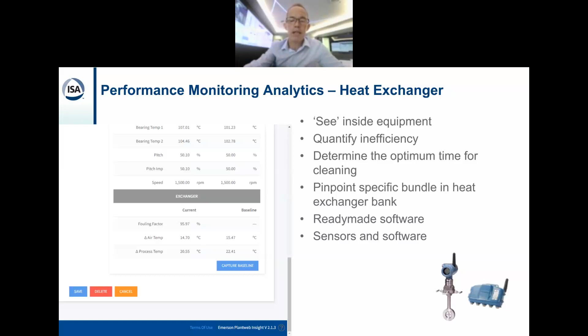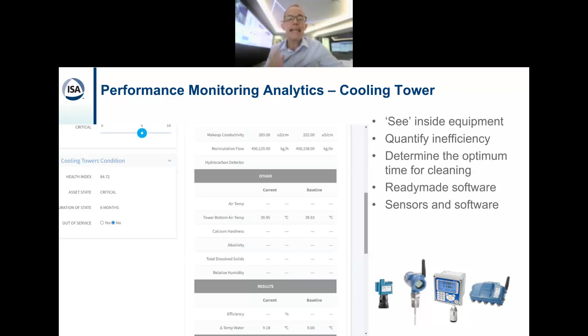Similarly, scaling and fouling of the cooling tower fill reduces efficiency, driving up energy consumption. Again, automation with software and sensors helps determine the optimum time for cleaning or fill replacement. Injection of anti-fouling chemicals can also be optimized. This way, data drives energy efficiency and sustainability.